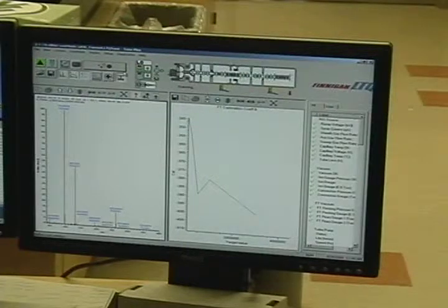I picked all your positive modes, transmission and excite every few months, probably around the same time I would do a full LTQ calibration, just out of habit. Mass calibration every week, which could be any mixture you want. If you find that your Ultramark hangs around for a while, replace it with other compounds like the polytyrosines from Sigma. You don't have to calibrate all the modes if you're not going to use them. Questions, thoughts, or comments?